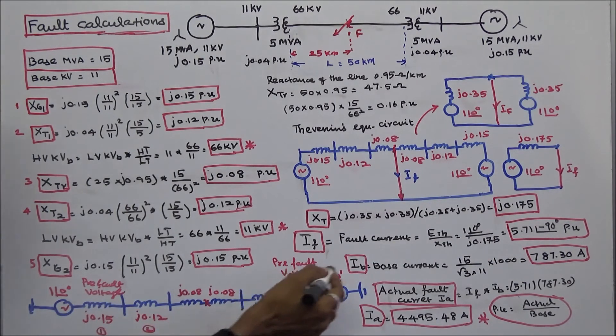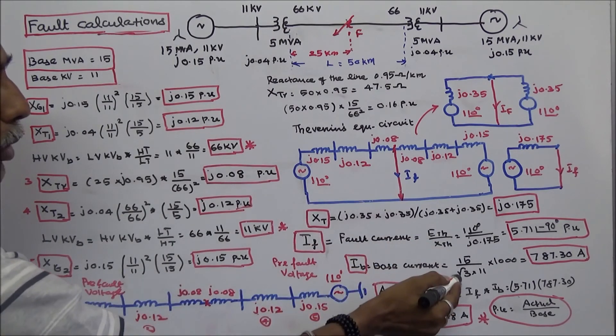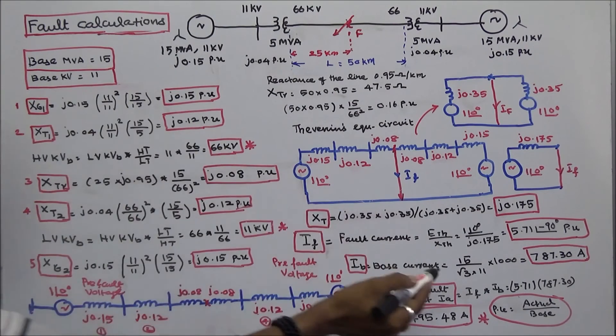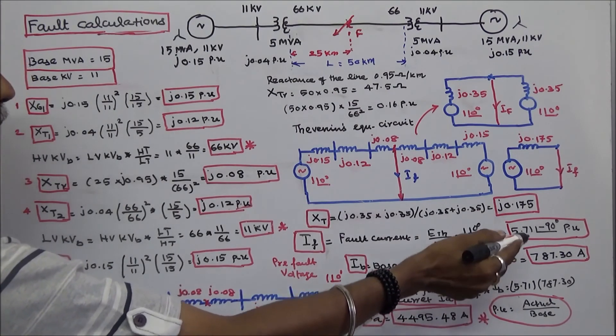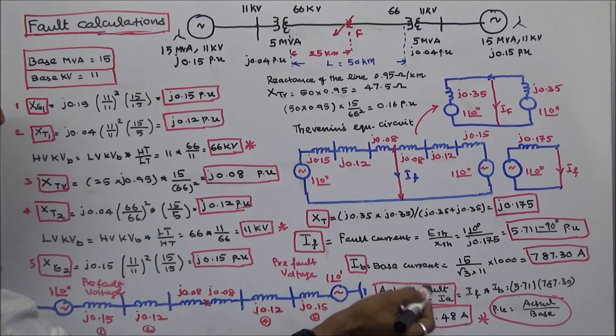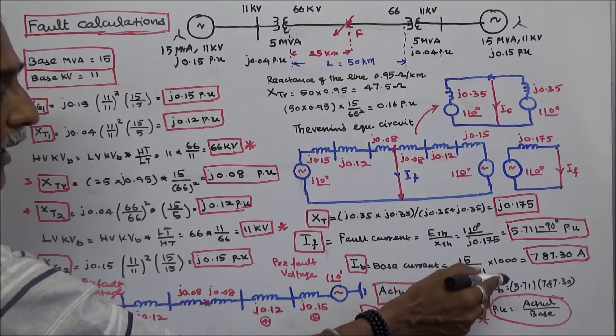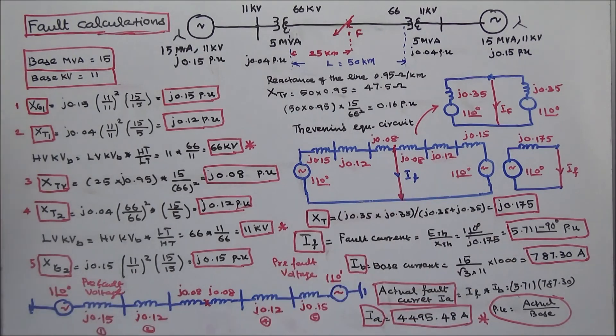Next, we calculate the base current. Base current equals base MVA (15) divided by (√3 × base KV × 1000) = 15 / (√3 × 11 × 1000) = 787.30 amps. The actual fault current is per-unit fault current × base current = 5.71 × 787.30 = 4495.48 amps.